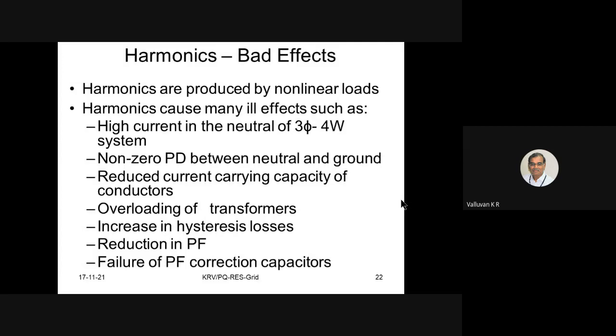As electrical engineers, we know that in a three-phase four-wire power distribution system, the three wires are the red, yellow, and blue phase wires, and the fourth wire is the neutral wire. In a balanced system, the current in the neutral conductor is zero. Maybe if there is a small unbalance in the load distribution, there will be a few amperes of current. So, for about the past 100 years, in a three-phase four-wire system in industry, people used to say the dimension of the UG cable is called 3.5 core. That means three cores are for RYB, and half the size of the core is for neutral. Neutral does not carry any current. It is only for reference.